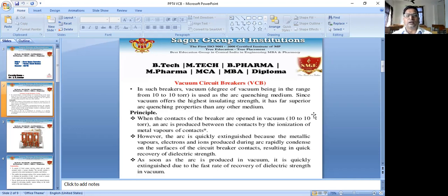The principle: when the contacts of the breaker are opened in a vacuum, an arc is produced between the contacts by ionization of the metal vapor of the contacts. However, the arc is quickly extinguished because the metallic vapor, electrons and ions produced during the arc rapidly condense on the surface of the circuit breaker contacts, resulting in quick recovery of the dielectric strength. As soon as the arc is produced in vacuum, it is quickly extinguished due to the fast rate of recovery of dielectric strength in a vacuum.